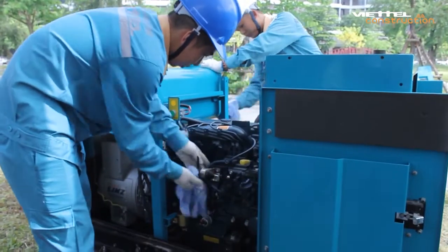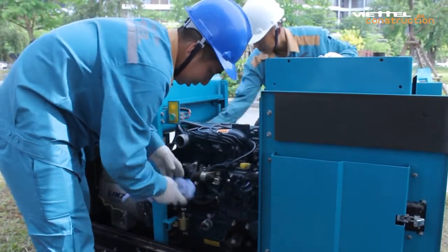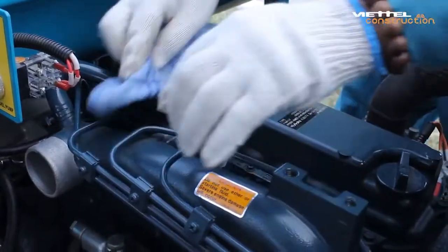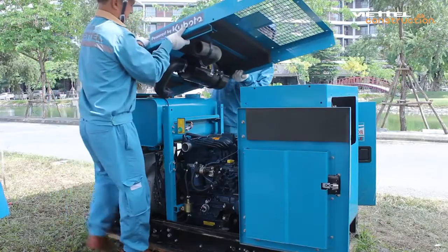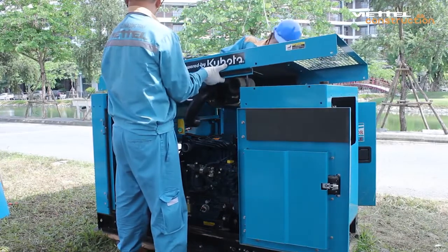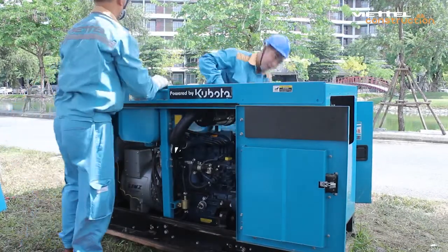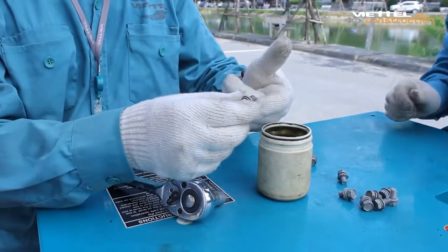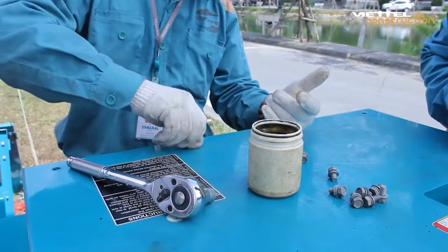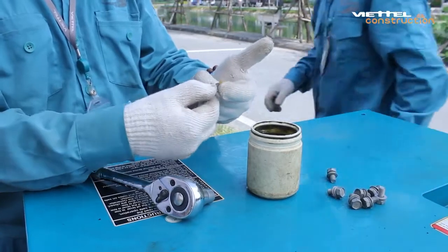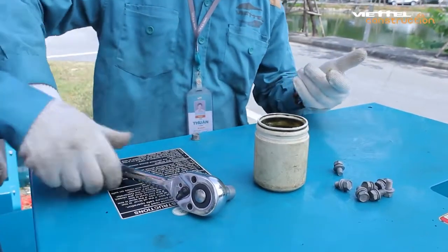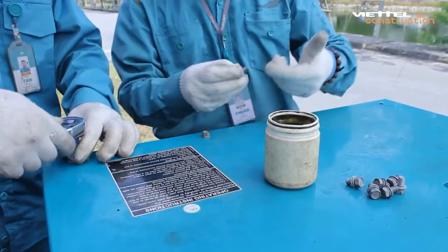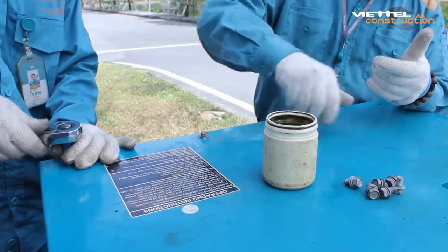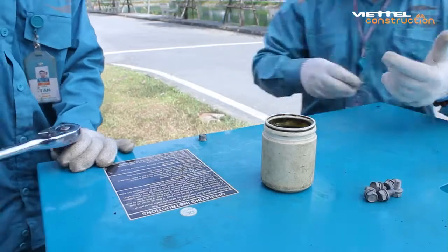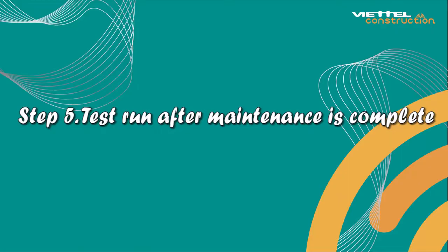Clean the whole body of the generator. Clean and repaint rusted areas. Reassemble the cover and the door to the body of the machine. For bolt joints, use a wrench to tighten bolts and nuts. Apply grease to all the positions of screws and bolts on the body of the machine. Test run after maintenance is complete.